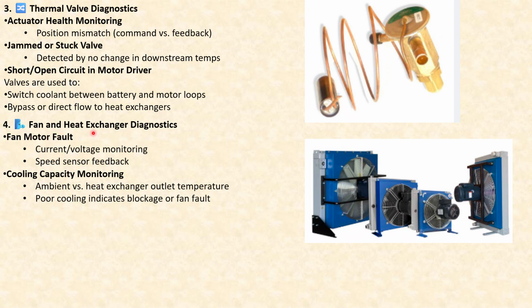Now, fan and heat exchanger diagnostics, fan motor fault. Okay, first you have to take care of the fan motor fault, current voltage monitoring, speed sensor feedback. With the help of the voltage monitoring and speed sensor feedback, the fan motor faults are thoroughly monitored. Now, when it comes to cooling capacity monitoring, you have to take care of this parameter. Ambient versus heat exchanger outlet temperature is a very important parameter that has to be kept under watch. Next is poor cooling indicates blockage or fan fault.